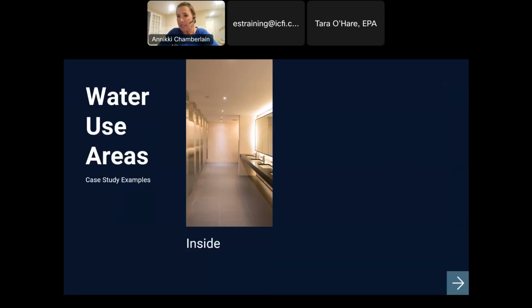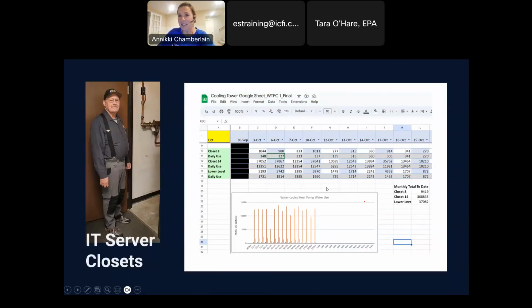Okay, so let's look at some case studies for some of the water use areas. So let's go inside. Here's a project. This was basically additional new meters with a manual data entry. One of my favorite people, Mike Peck, had a facility with 7 water-cooled condensers for the IT closets. He said, hey, I was doing a cooling tower project, can I borrow one of those? I want to put it on these water-cooled condensers and see how much water they use. Within 1 month, they were able to collect enough data, and they replaced 4 of them with air-cooled systems, so that's good. And on the remaining 3, we installed clamp-on meters.